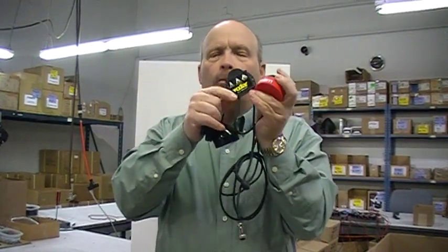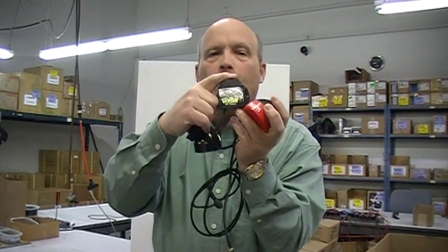In other words, the Tri-Beam is designed to function at minimum gain with mechanical switching. If you turn up the gain with the Tri-Beam, the signal actually distorts because it's not really designed for a wider listening area. The crystals do not perform very well. But with the ProView, you can literally adjust it from a very narrow 9-degree angle to even a 40-degree receiving area if you would like, if you turn up the gain. But again, with all transducers, you want to keep the gain as low as possible to avoid distortion and make sure you have a sharp, crisp signal.